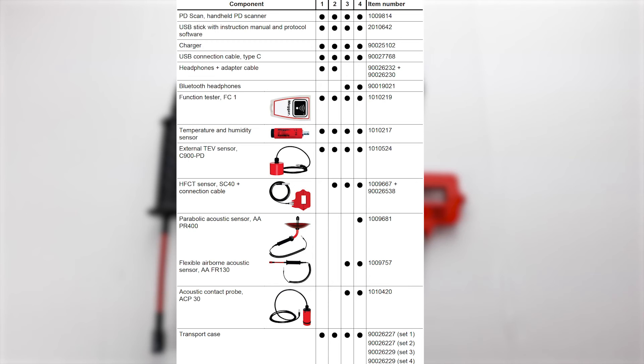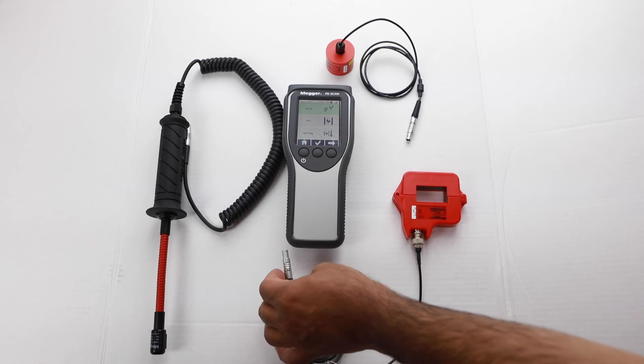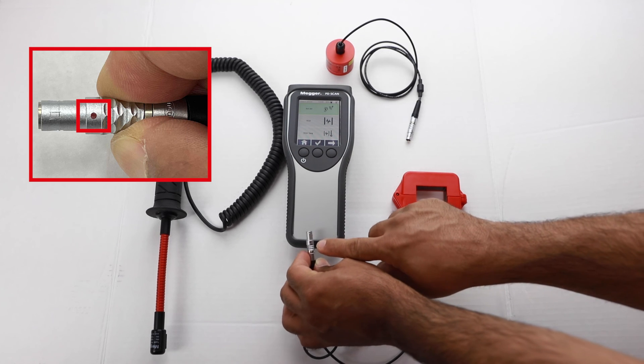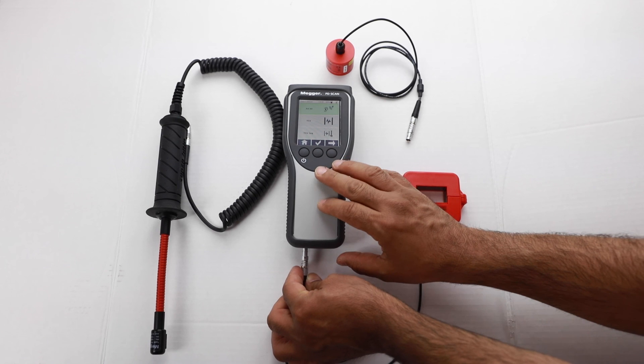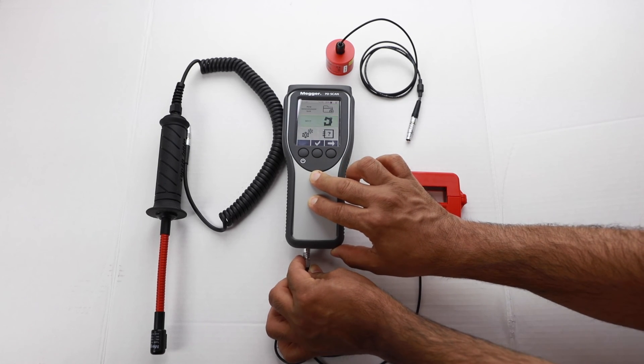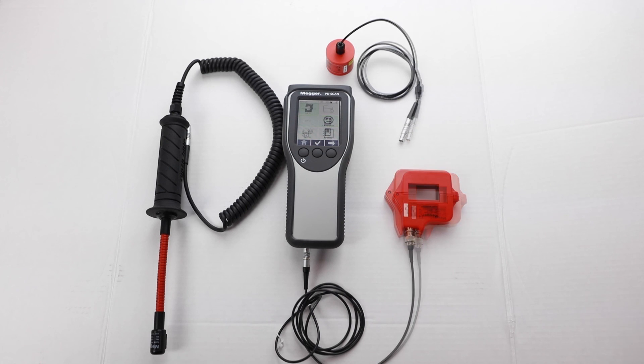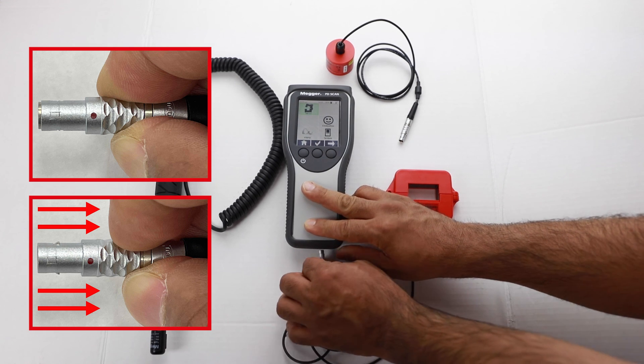The PD scanner has a number of different packages that come with different external sensors for a variety of tests. We will cover each of these sensors in another video. For now, we will connect a high frequency CT or HFCT to the test set. With the red dot facing up, we will plug the sensor into the bottom of the test set. Once we've installed the sensor, the menu will change to show that this new sensor is available. To disconnect the sensor, simply pull the spring back on the lead.